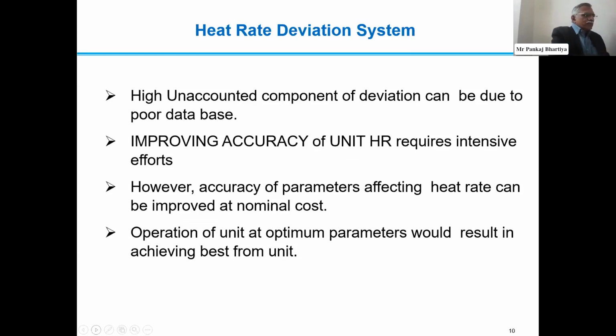Yeah, so the high unaccounted component of the deviation can be due to the poor database as well. And improving the accuracy of your unit heat rate requires intensive efforts with reference to that. However, the accuracy of parameters affecting the heat rate can be improved at a nominal cost. I mean, we need not consider all the parameters that we are measuring, but we can consider the specific parameters which are important from the assessment point of view. So operation of unit at optimum parameters would result in achieving the best form of unit heat rate. So that is what we are going to focus on through the various systems that we devise.